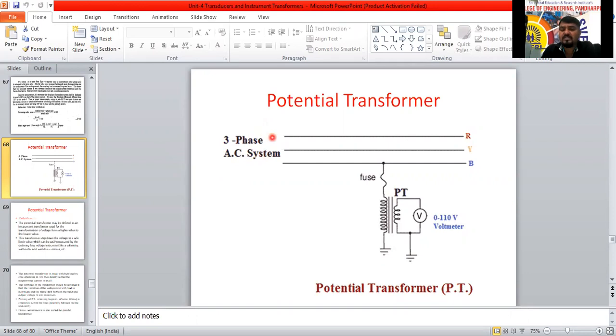Divide for the voltage system here. For the potential transformer, we use for the current, IS by N. For the voltage, we use N into VS. N is nothing but the ratio we are using, that ratio or turns ratio only. IP divided by IS equals N, we are going to use. Based on that, this N, the ratio, we divide for the currents and multiply for the voltages on the secondary side.